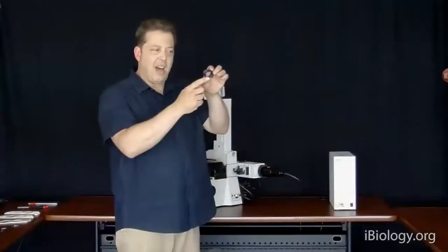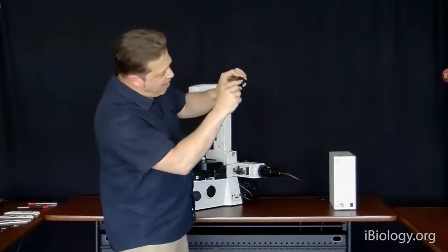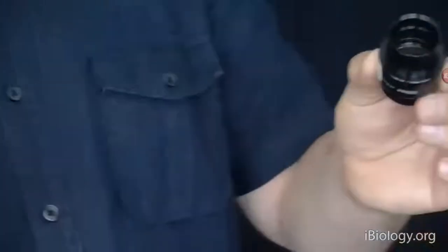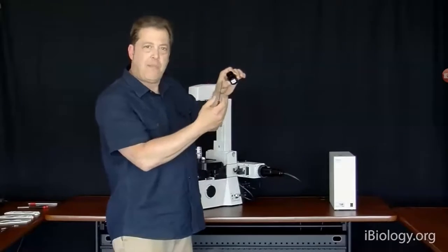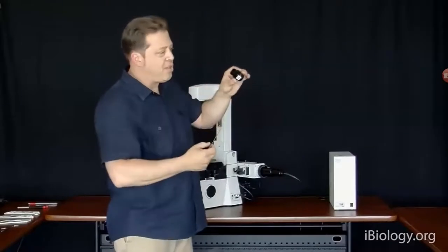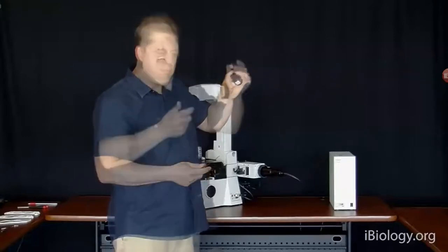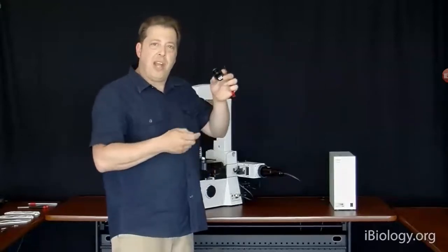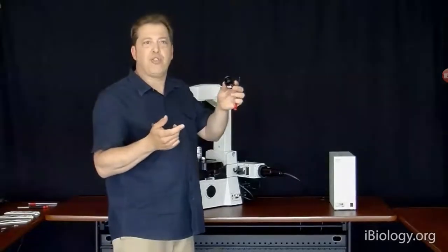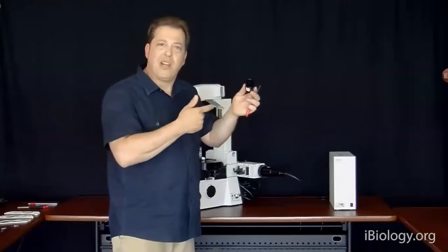The other thing I wanted to show you is an area that actually has an accessible field plane inside the eyepiece. And you can see I just unscrewed this little ring, and there's a little shelf inside this eyepiece. And that shelf is where we would put what's called an eyepiece reticle, which is basically a small scale bar that's printed on a piece of glass that we would be able to put onto the eyepiece of the microscope. It's a nice accessible image plane in the microscope, and it's a good location if you wanted, for example, to block certain wavelengths of light.